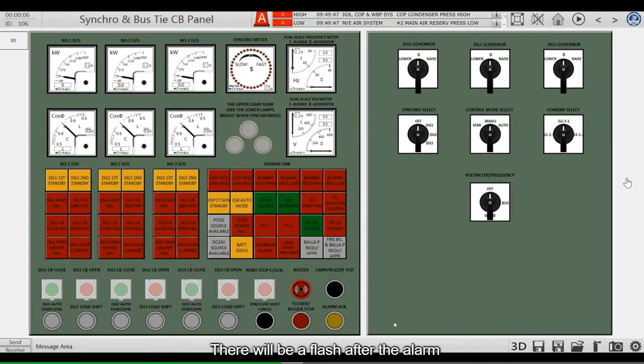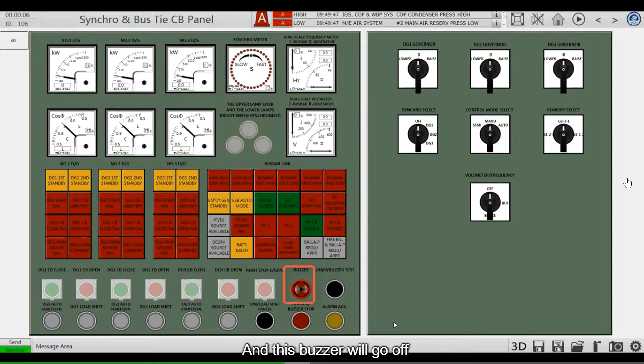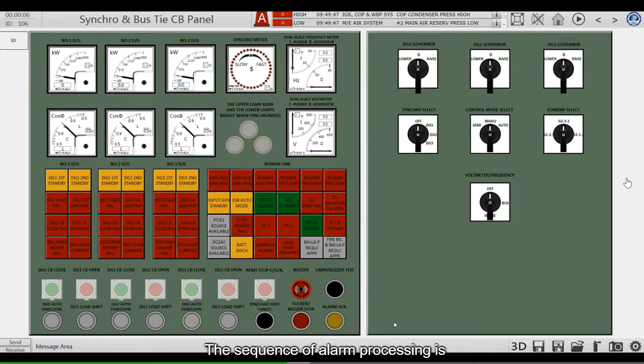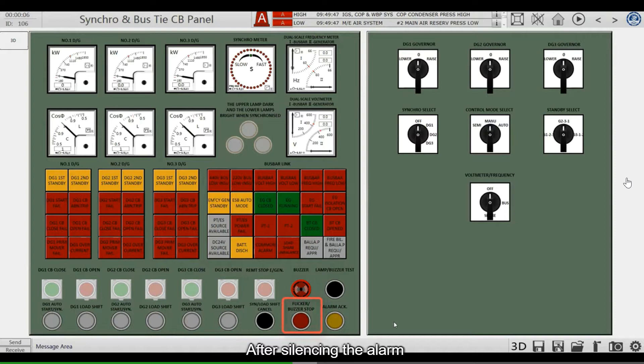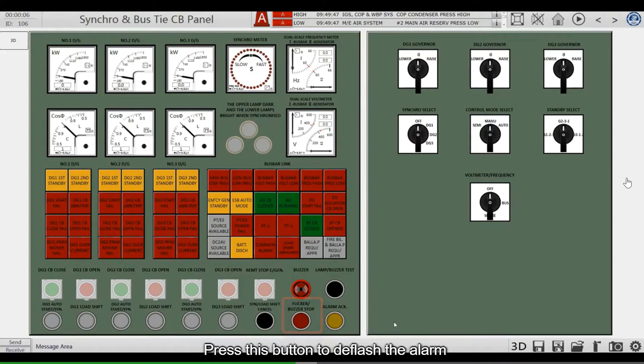There will be a flash after the alarm, and the buzzer will go off. The sequence of alarm processing is: press this button to silence the alarm. After silencing the alarm, the alarm needs to be deflashed. Press this button to deflash the alarm.